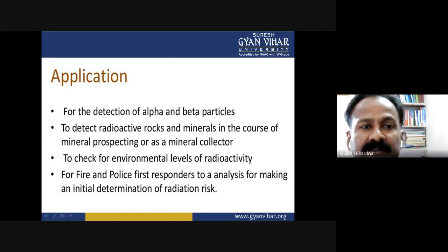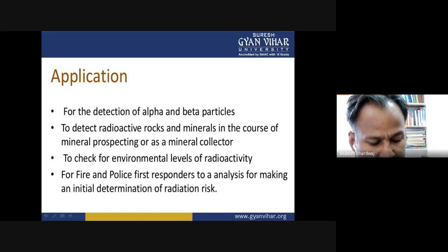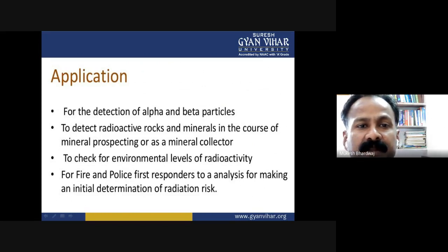The main characteristics of the GM counter and its limitations: the height of the pulse voltage is constant and does not depend on the primary ionization. Pulse voltage is produced even if a single electron-ion pair is generated in the chamber. After the entrance of an ionizing particle, the paralysis time is quite large, so it limits its uses. The height of the pulse voltage does not depend on the energy of the ionizing particle. Therefore, the GM counter cannot be used for measuring the energy of particles.